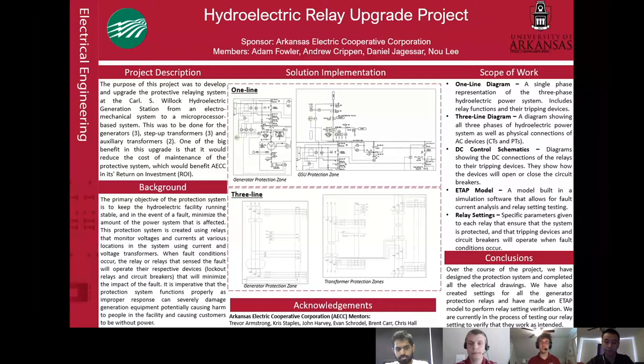As a part of this project, we were tasked with creating three different kinds of drawings: the one-line and three-line diagrams, which you see in the solution implementation section of our poster, as well as the DC control schematics. These three kinds of drawings were then compiled into our ETAP model, which allowed us to simulate how the system would react to different stimuli in terms of voltage, current, and frequency. The models combined with our own calculations were then brought together to come up with our relay settings, which were the parameters for each of the different kinds of relays that needed to be set. In our solution implementation section, you can see some of how the protection zones overlapped, as well as the lockouts or the relays that would shut down parts of the system when something went wrong. Those lockouts are marked in green, and in the three-line section, you can see more of that overlap.